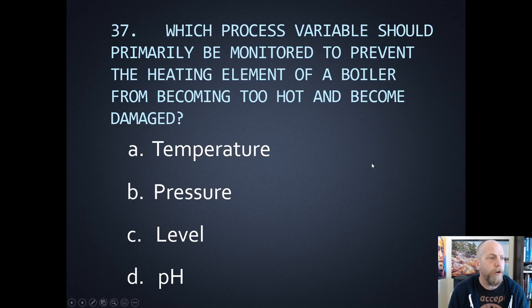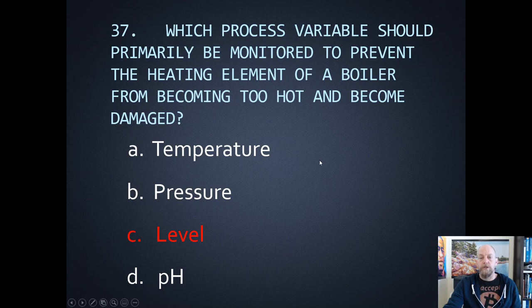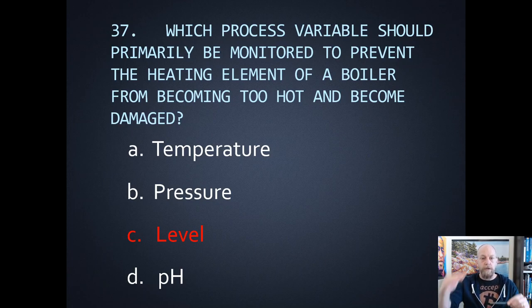Number thirty-seven: which process variable should primarily be monitored to prevent the heating element of a boiler from becoming too hot and being damaged? The heating element ultimately controls the temperature, but in order to prevent it from burning out, we need to control the level — we need it always immersed in the water so it can create the steam. We're always looking at the level being maintained so it doesn't go below the element.